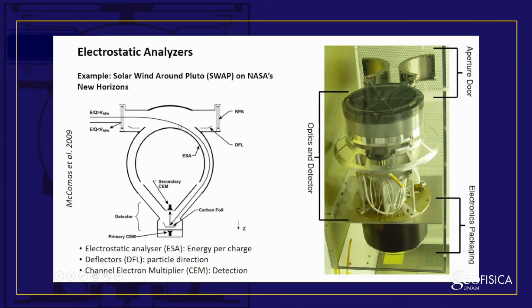Now, when they enter this region, they are about to enter the electrostatic analyzer, which is two homocentric, partially spherical shells. This is the inner electrostatic analyzer dome, and this is the outer electrostatic analyzer dome, right? So now if we apply a specific voltage difference between these two domes, we can bend the particle trajectories, and if the particle has a specific energy per charge, it can make it all the way through the electrostatic analyzer and continue straight to the detection area. So here we have a detector that will tell us, I record 1, 2, 3, 200 particles. So those that make it through. So a specific voltage difference makes a specific energy per charge get detected.